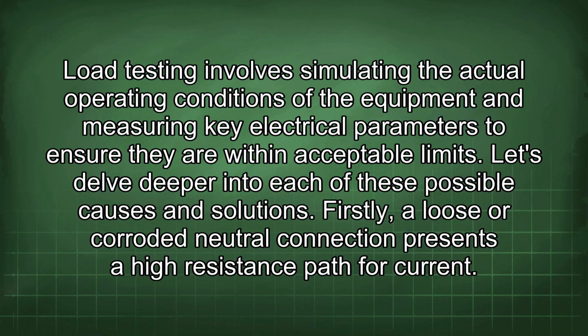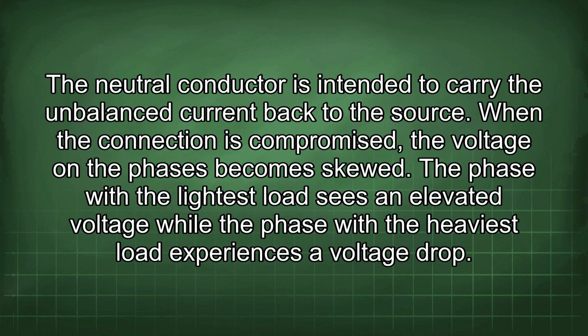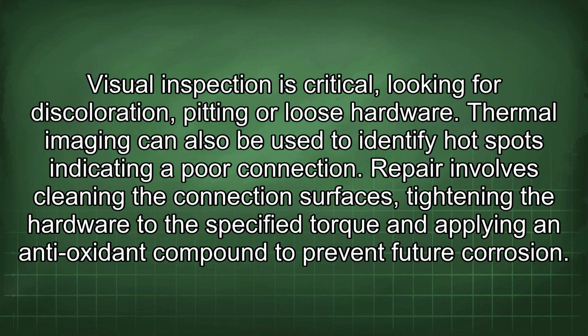Firstly, a loose or corroded neutral connection presents a high resistance path for current. The neutral conductor is intended to carry the unbalanced current back to the source. When the connection is compromised, the voltage in the phases becomes skewed. The phase with the lightest load sees an elevated voltage, while the phase with the heaviest load experiences a voltage drop. Visual inspection is critical, looking for discoloration, pitting, or loose hardware.